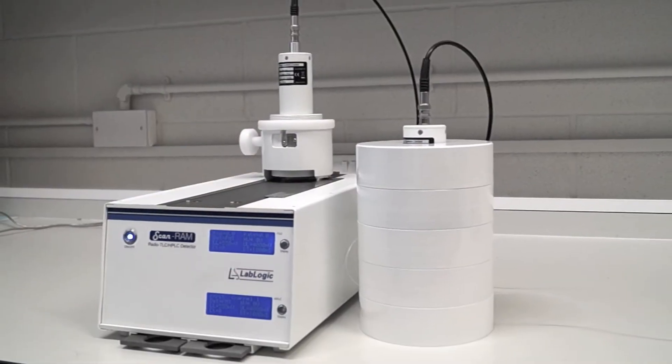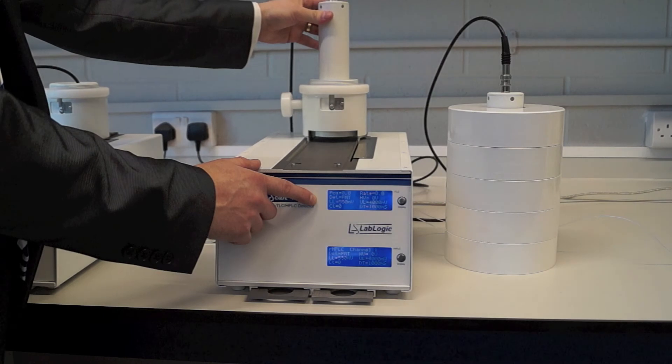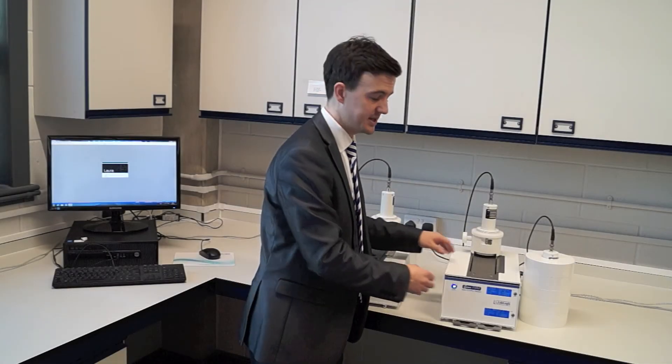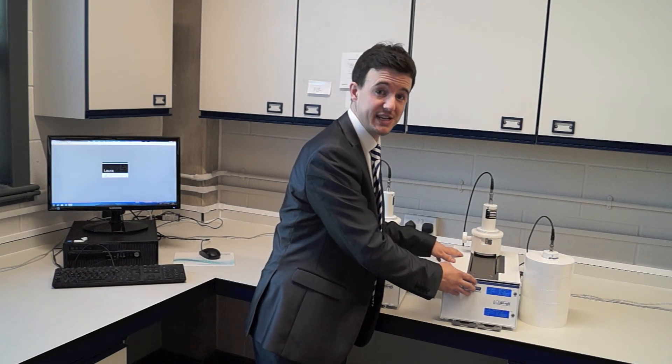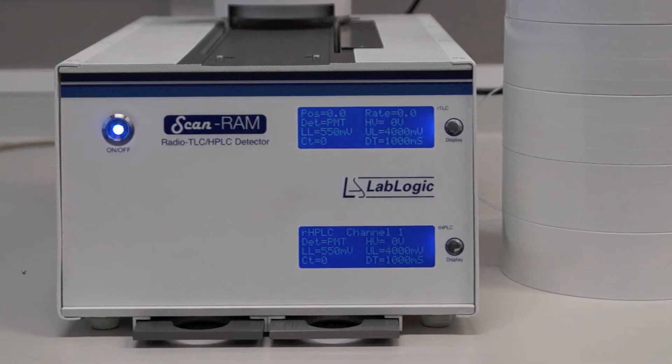Another product in the QC range is our Scan-RAM system, which is a very unique solution combining two technologies in one compact unit: radio TLC and radio HPLC. One point to note is that the electronics for TLC and HPLC are totally separate from one another, which means that you can use both systems independently and simultaneously in the lab.